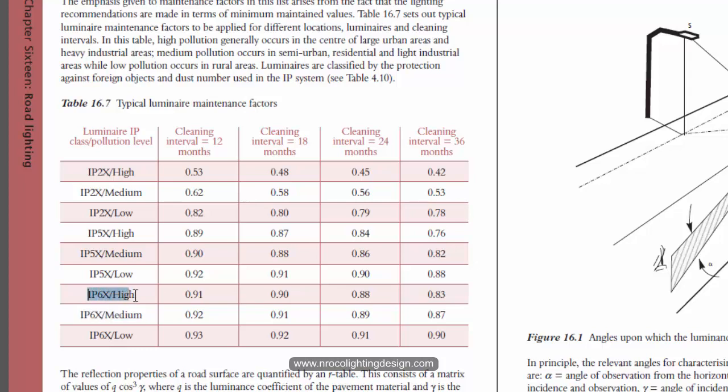But your IP rating is IP65, you can have 0.91 or 0.90 or 0.88 or 0.83 depending on how long the luminaire will be cleaned up.